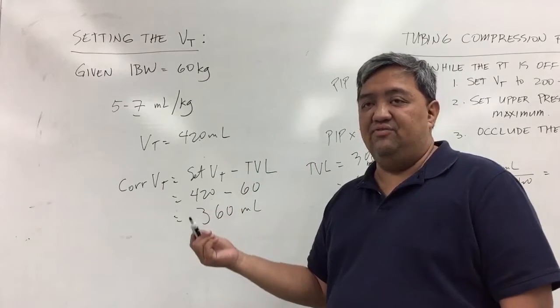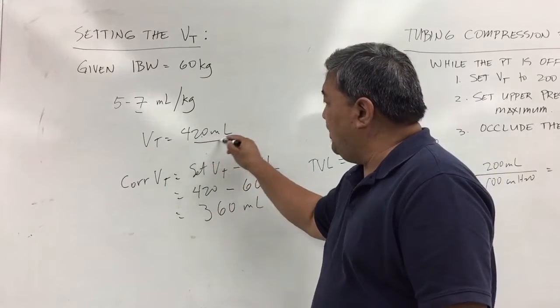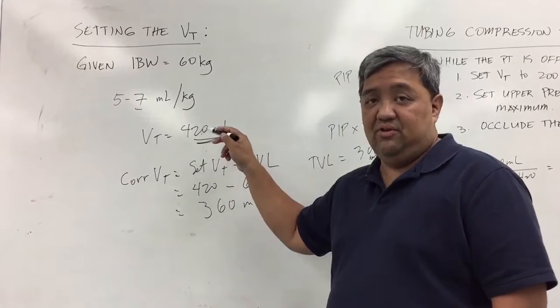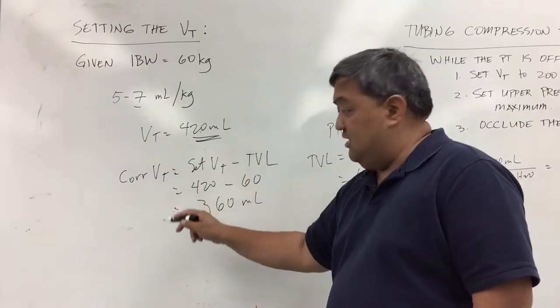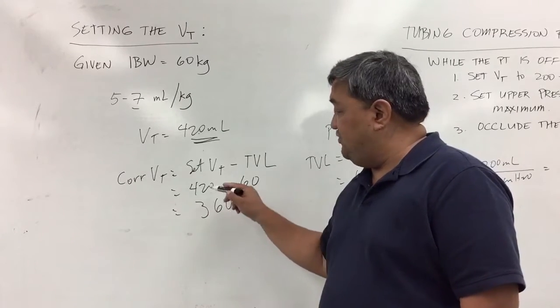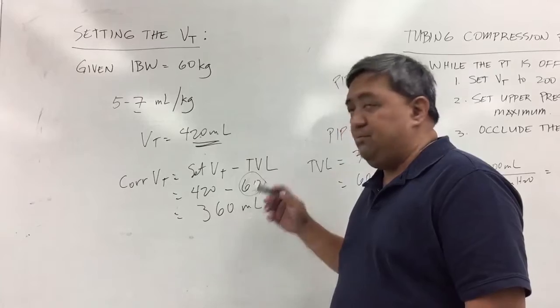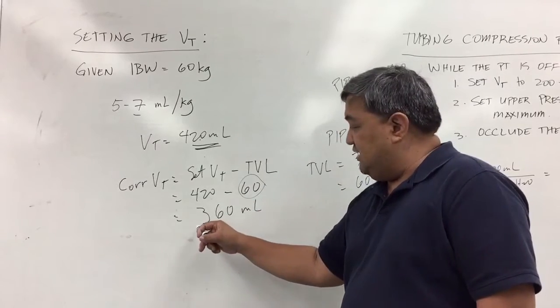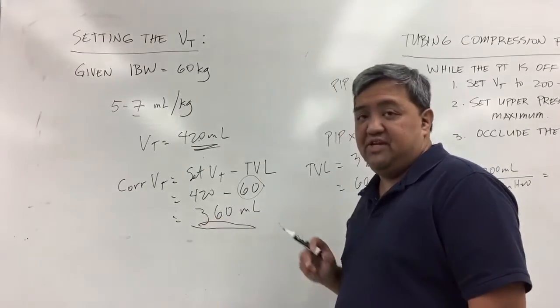Your set tidal volume, if you put in 420, your return volumes may not get the 420 back. It may even get something as low as 360 just because of the 60 ml tubing volume lost in the circuit. This is the corrected tidal volume that the patient is receiving.